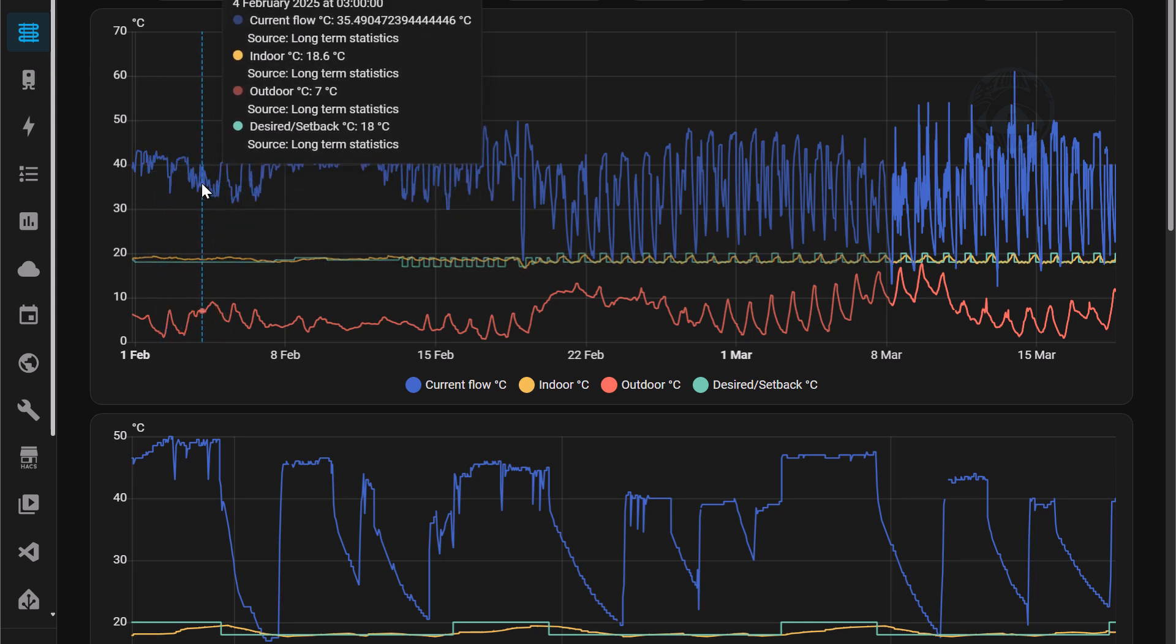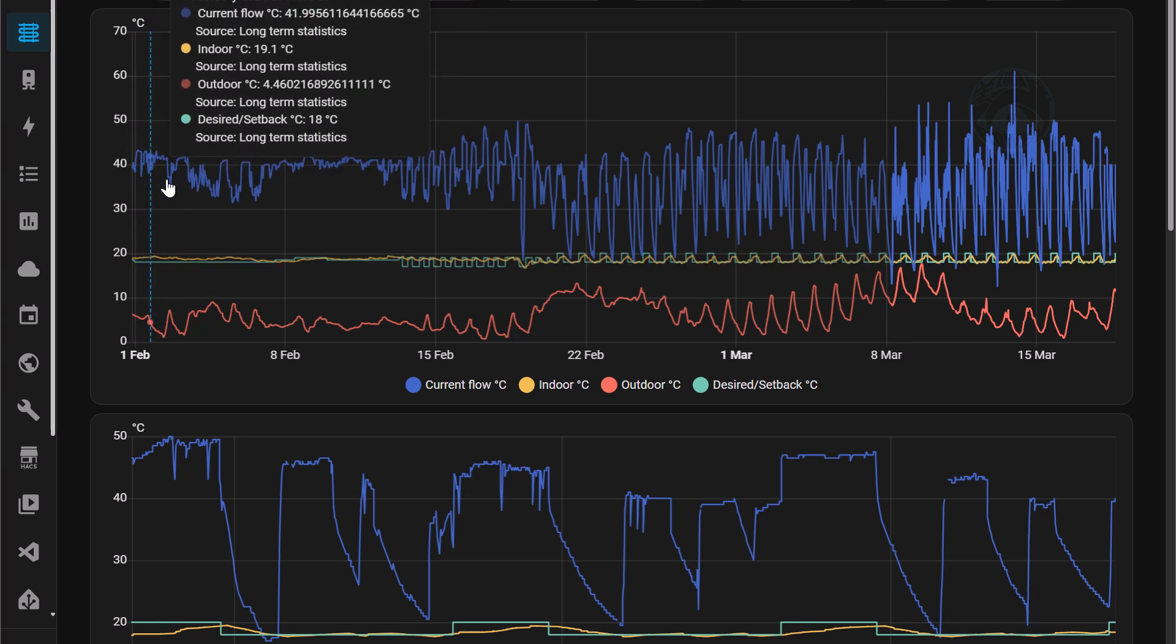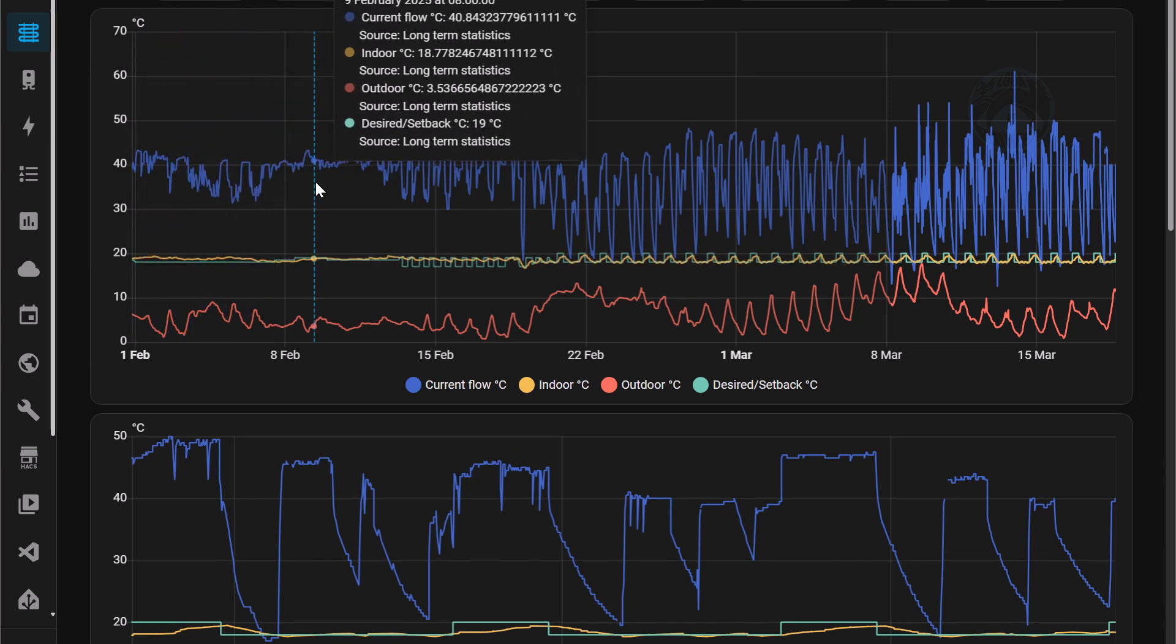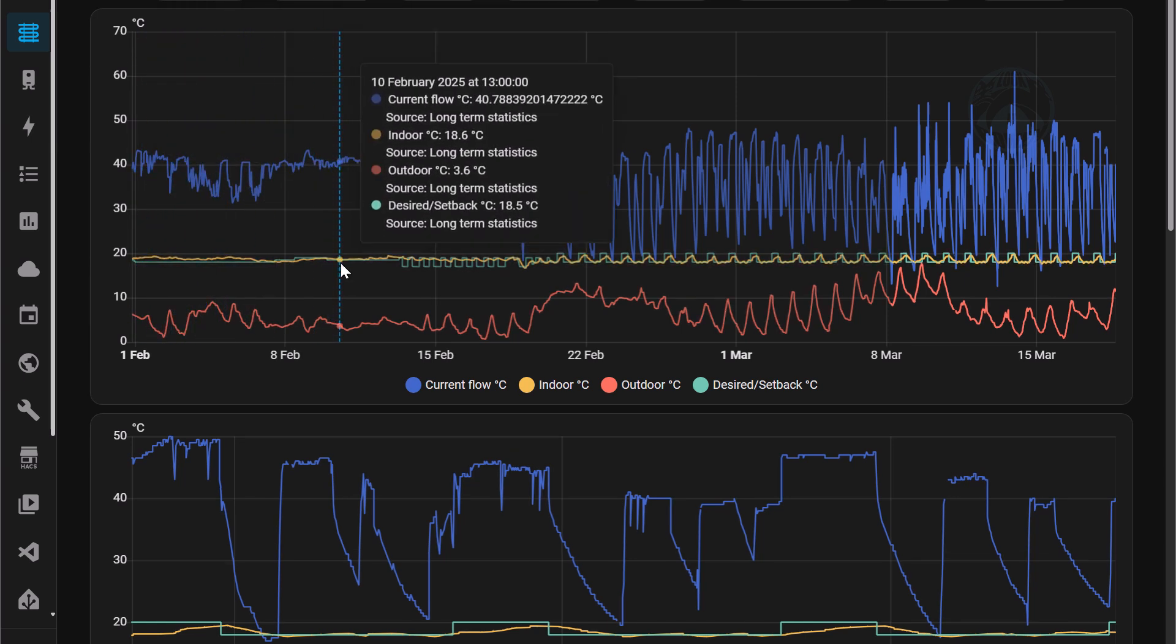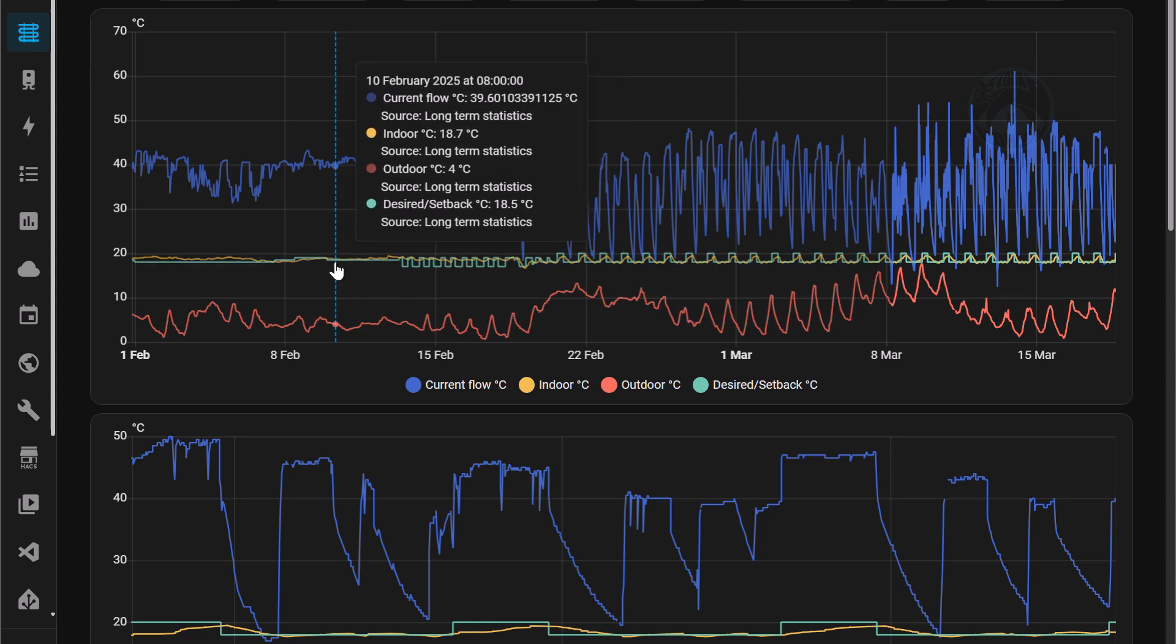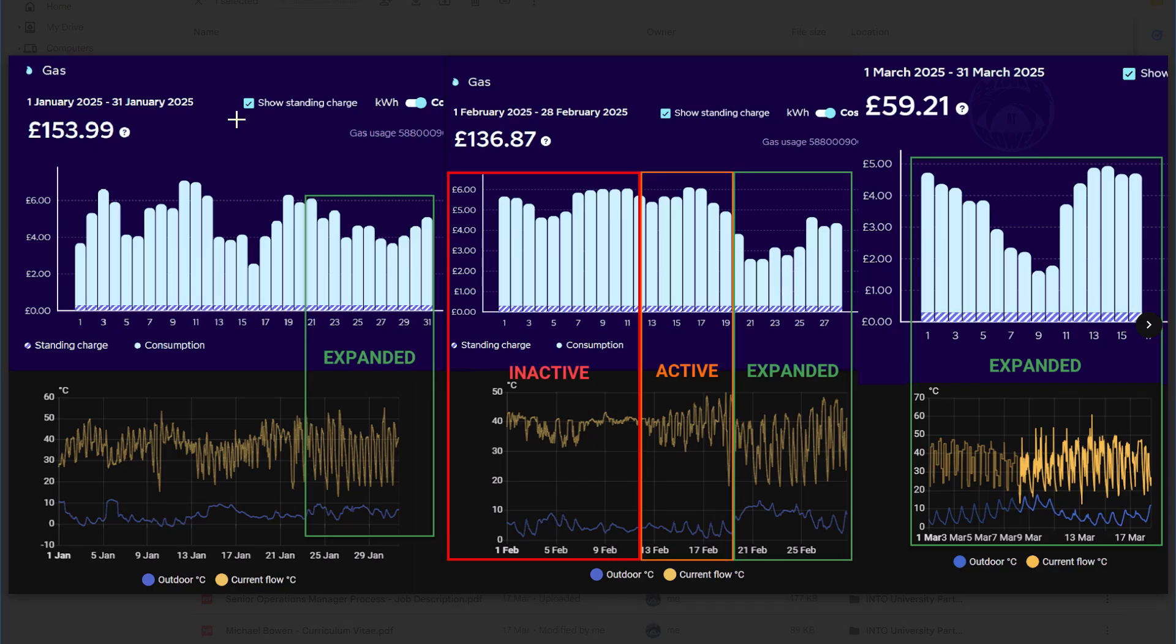The boiler is on 24/7 and what I noticed in this first couple of days or even a week of February was that the gas bills were a lot higher than the last 10 days of January when I was running room temperature mod equals expanded. Now there is one caveat I should point out and I'll show you here on the last 10 days of January. The temperature during that period was a lot higher than it was in the first 10 days of February and I think that has made a difference.